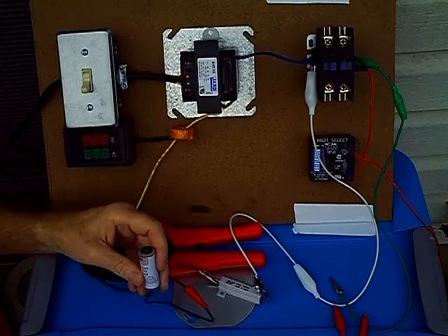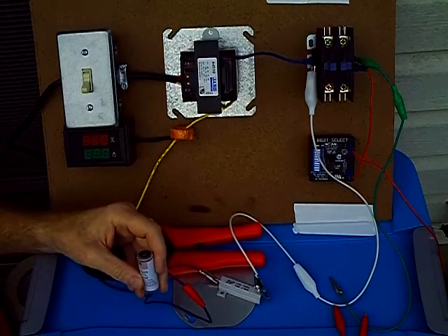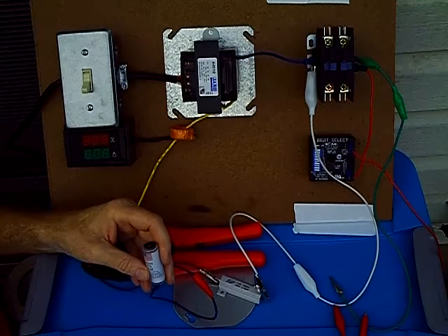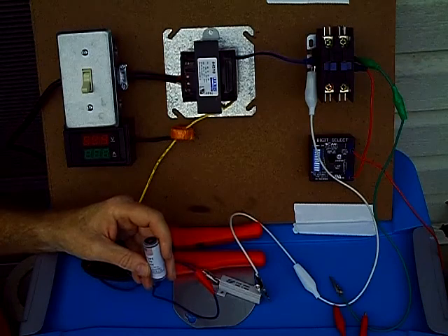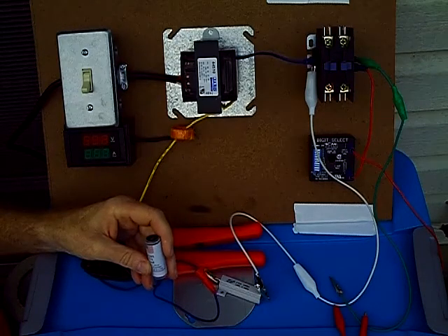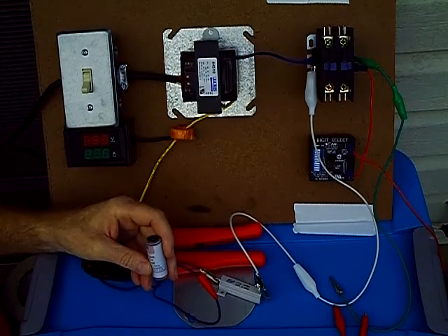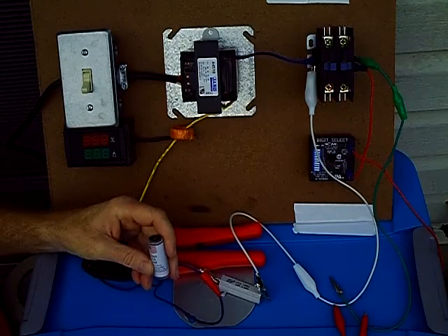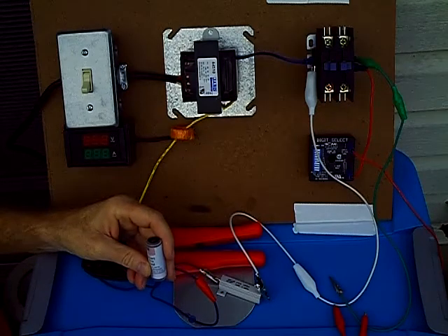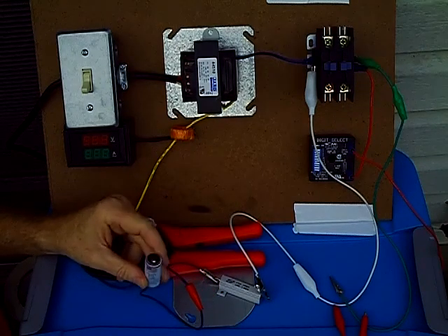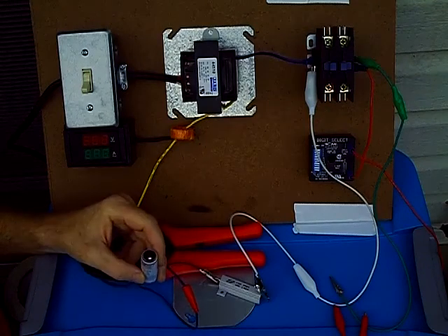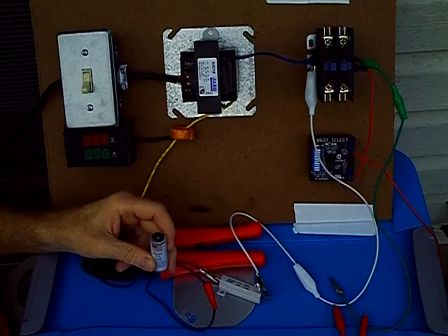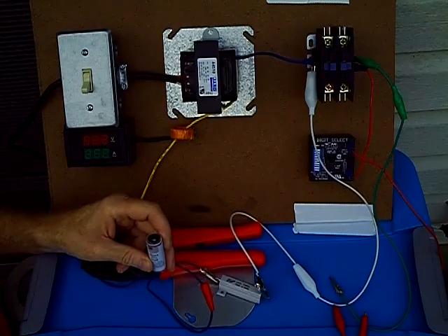Now, any decent service technician knows a 40VA transformer, how much current it can handle. So you take the 40VAs and divide it by the secondary voltage of 24 volts, that'll give you 1.66 amps that the typical 40VA transformer can handle. Anything above that, well, the transformer's going to burn out. So what I'll do is demonstrate the ShortPro just to show how fine-tuned it is to a 40VA transformer short, and it can catch that 1.5, 1.6 amps short.